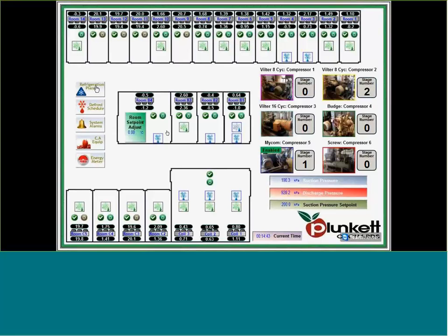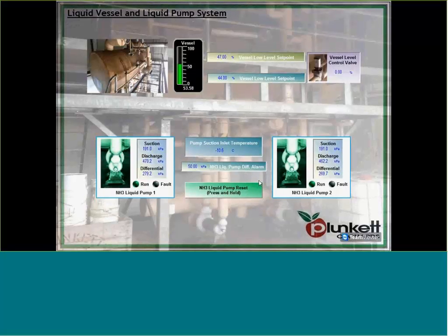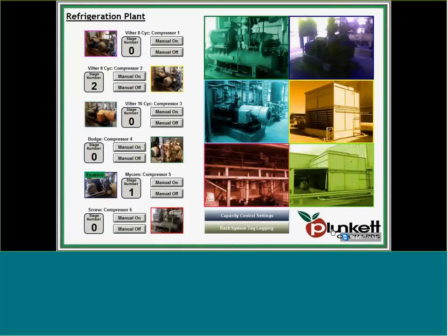In the refrigerated plant room, we move to this screen, which shows a lot of visuals. So the plant, the actual physical pictures of the plant we used, so people could tell what area of the plant they were looking at. This really helped out with things like the liquid pumps, so people could actually look at the photo, see what the liquid pump was, and go and see when general faults had occurred. We also used a few general symbols there, straight out of the InduSoft library. Worked great.